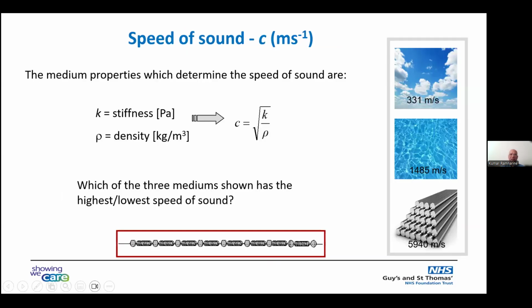Okay, so how fast does the ultrasound pulse travel through tissue? And what does the speed depend on? The speed at which an ultrasound wave travels is dependent on the medium properties. So the speed here is given by the square root of the stiffness divided by the density. So the stiffer the tissue, the faster the ultrasound propagation speed.